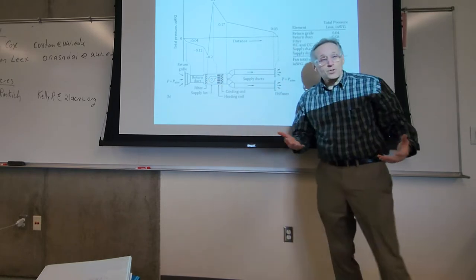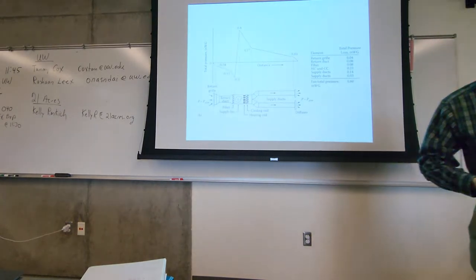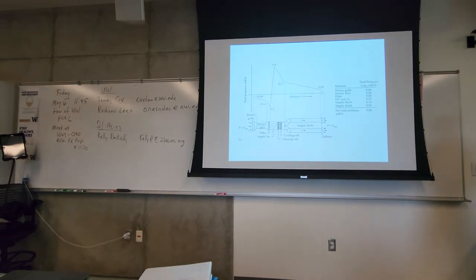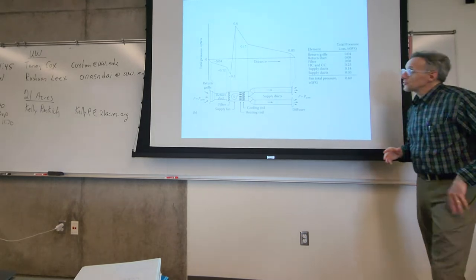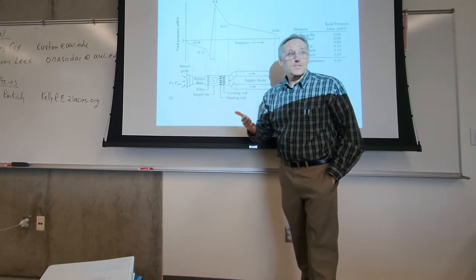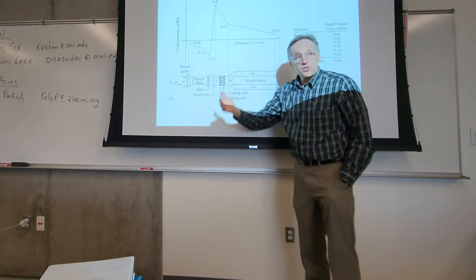and nowadays because of COVID and fires, we're starting to specify more efficient filters that take out more particulate, finer particulate, and that's much higher pressure drops, like MERV 11, MERV 12, MERV 13 filters are now recommended instead of the MERV 6 or 7 that I was using until a couple of years ago. And then you get into HEPA filters for hospitals and things like that. Those are really highly efficient, but they also have pretty high pressure drop. And you have to make sure to factor that into your design.